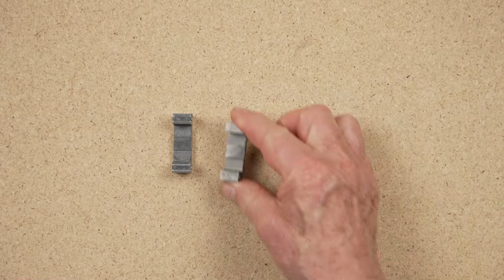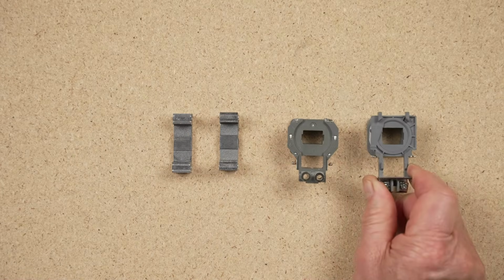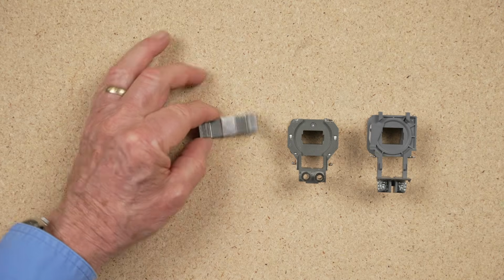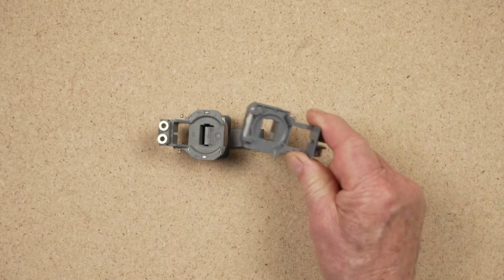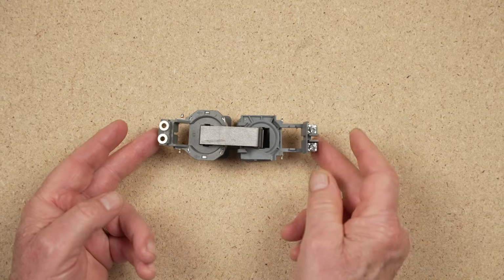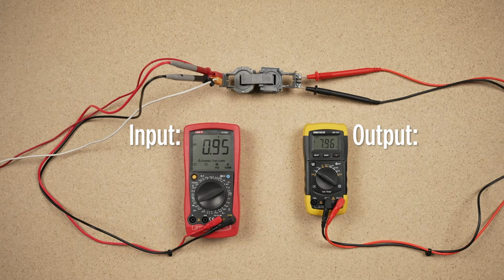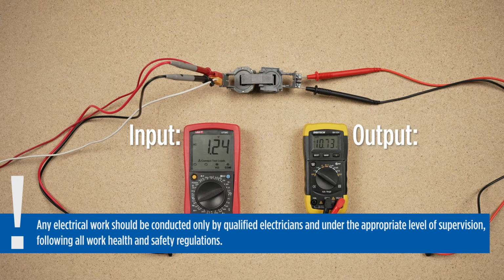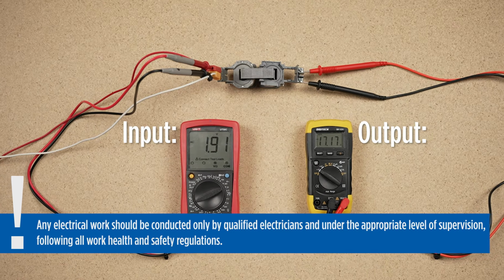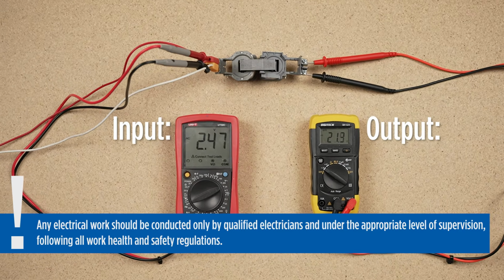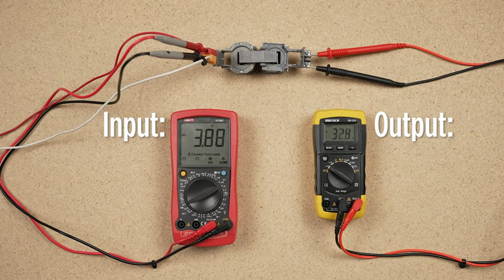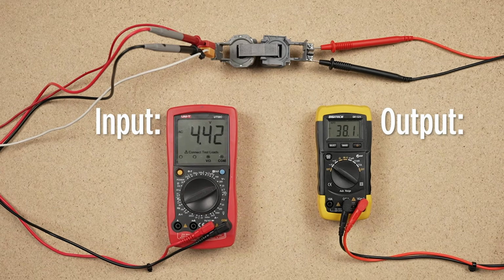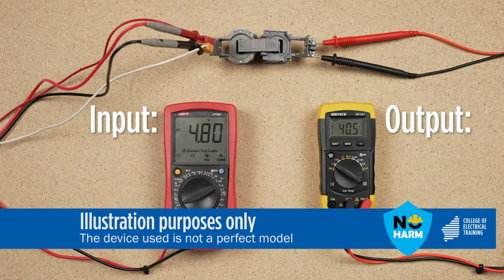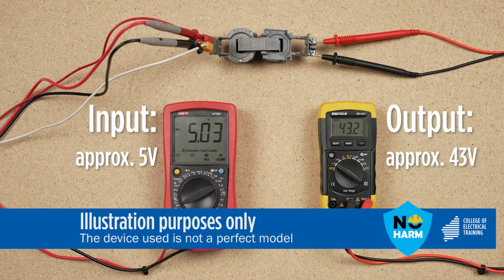A CT works like a step-up voltage transformer. A double-wound step-up transformer has more turns on the secondary winding than on the primary winding. This results in a higher output voltage than the input voltage on the primary winding. The value of the output voltage is determined by the ratio of secondary turns to primary turns on the transformer.